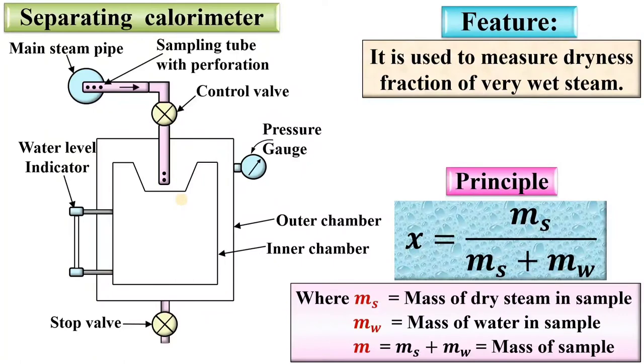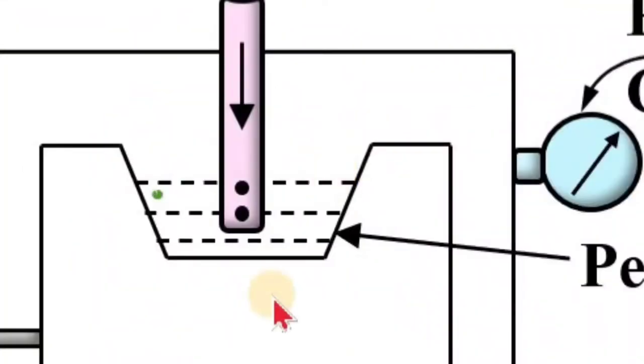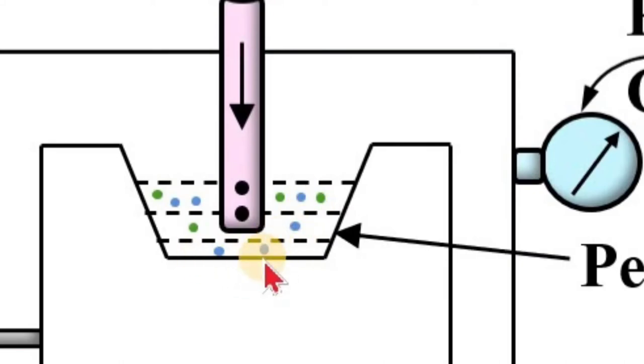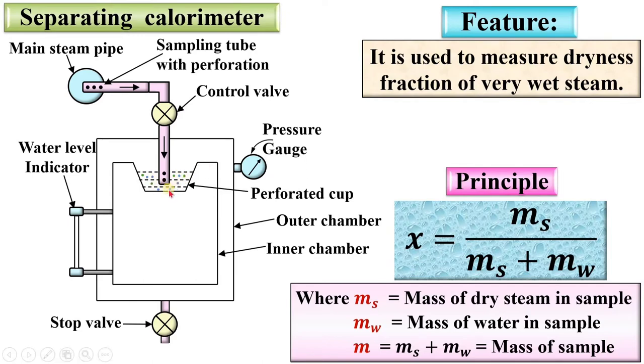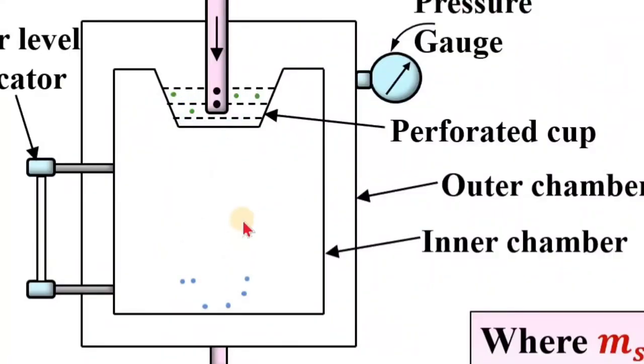Now let us see the animation. First, steam is taken from the main steam pipe through the sampling tube, and then it strikes on this perforated cup, so it is collected here. This steam contains water particles as well as steam particles — the green color represents the steam particles and the blue color represents the water particles. Since water particles have more density than steam particles, they are collected at the bottommost portion of the perforated cup.